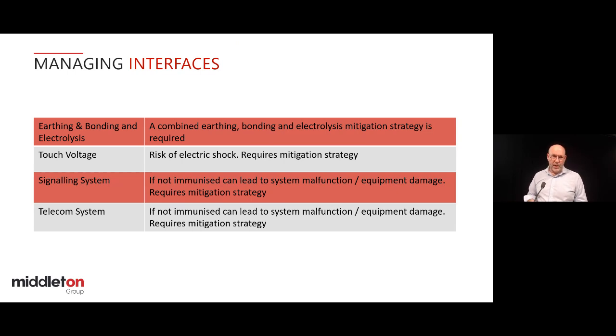Also telecom systems, same sort of issue. Harmonics and return currents finding their way into telecommunication circuits is usually not good, so again, immunisation is normally required. The EN standard 50122-3 sets out the approaches you can use to manage the interfaces between AC and DC railways.